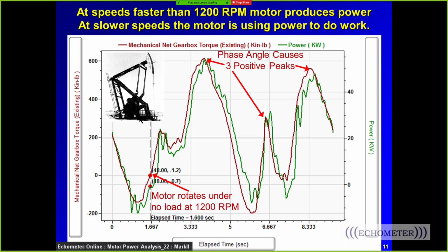with rod loading, and it results in a smaller gearbox and a lower amount of torque. And so when you look at a Mark unit, the net torque curve doesn't have two peaks and two valleys. It has usually two large peaks. This is the peak here picking up the rods. This is the peak here picking up the weights.